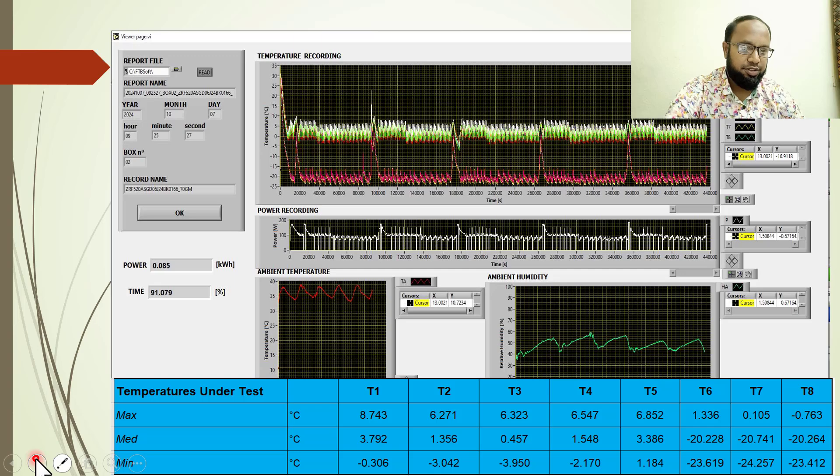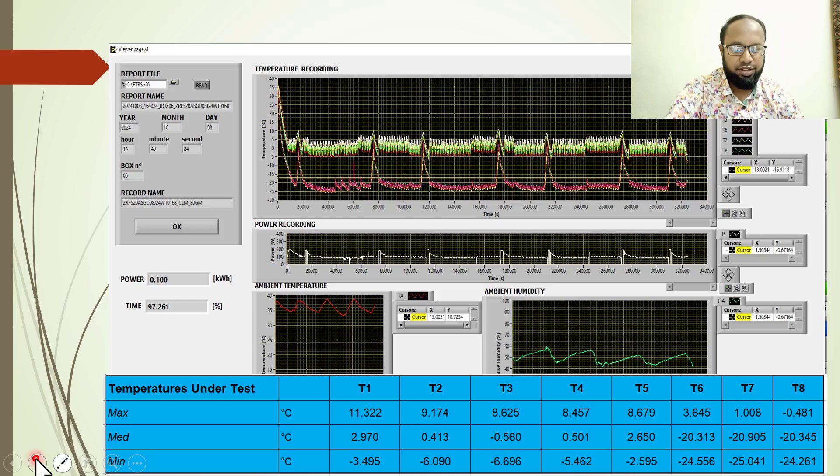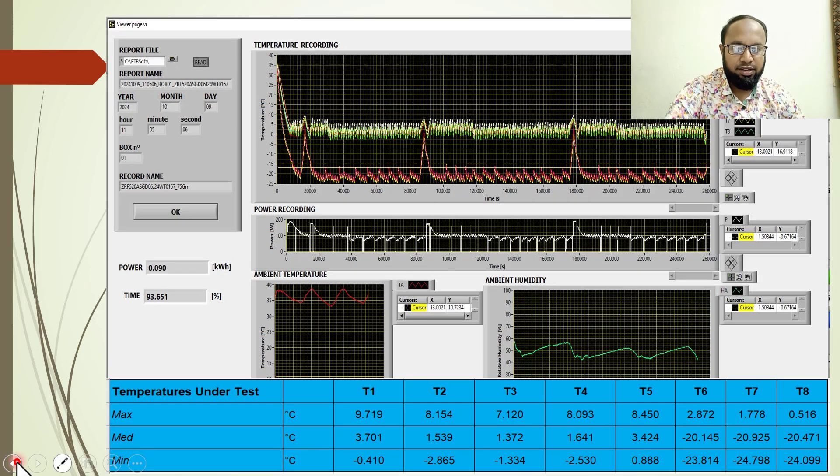Comparing the datasets, this one is the best. We are analyzing it because the refrigerator is cycling well, and after 11 hours it is defrosting continuously. The temperature achieving data shows the temperature going down immediately, which shows good performance. For this reason, we are selecting this refrigerator as performing very well.